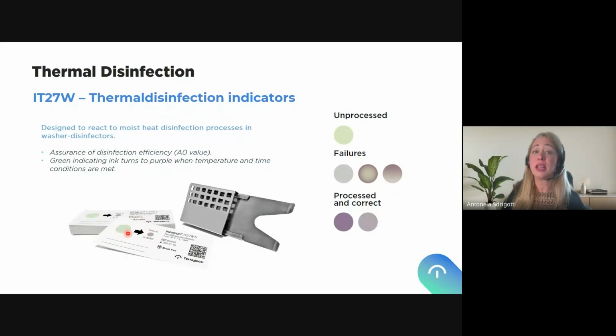And we have a green ink that turns to purple when time and temperature are correctly integrated to reach the A0 value. As you can see here, the unprocessed color is this one, and the failures will be seen in different shades of color between the initial and the reference. You see here, this is the reference one. You have it printed on your indicator so that you don't have any hesitation about which is the final color. If it's darker, it means that you just exceeded the minimum to guarantee disinfection. So if it's darker than the reference, it is better. And of course, as you can see here, it can be used with the same holder as we use for the washer indicator. So two different holders, right? One for the washer indicator and the other for the thermal disinfection indicator. This way, we make sure we monitor both different steps of a washer disinfection process.